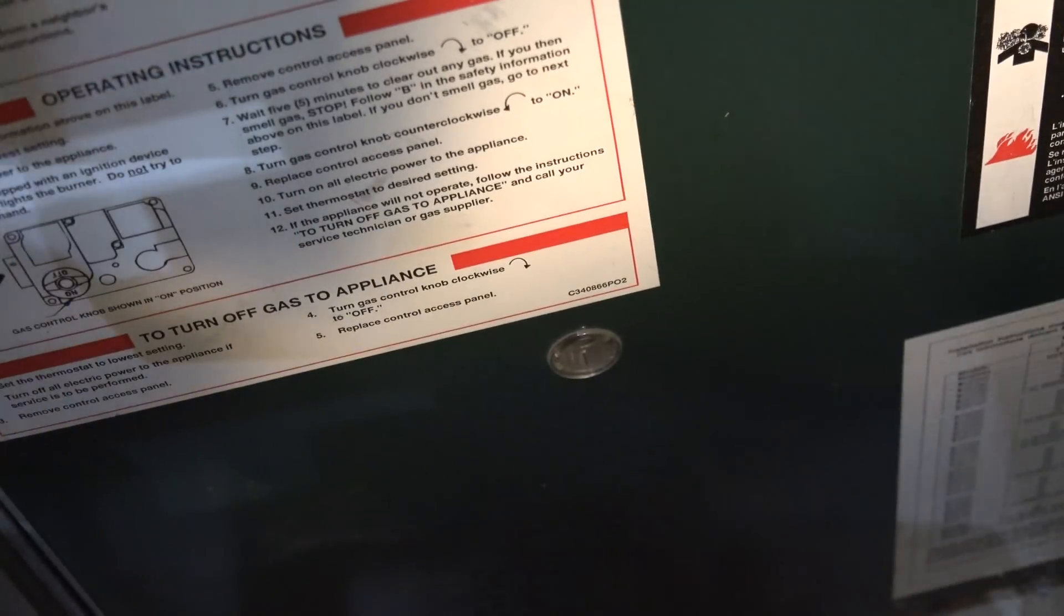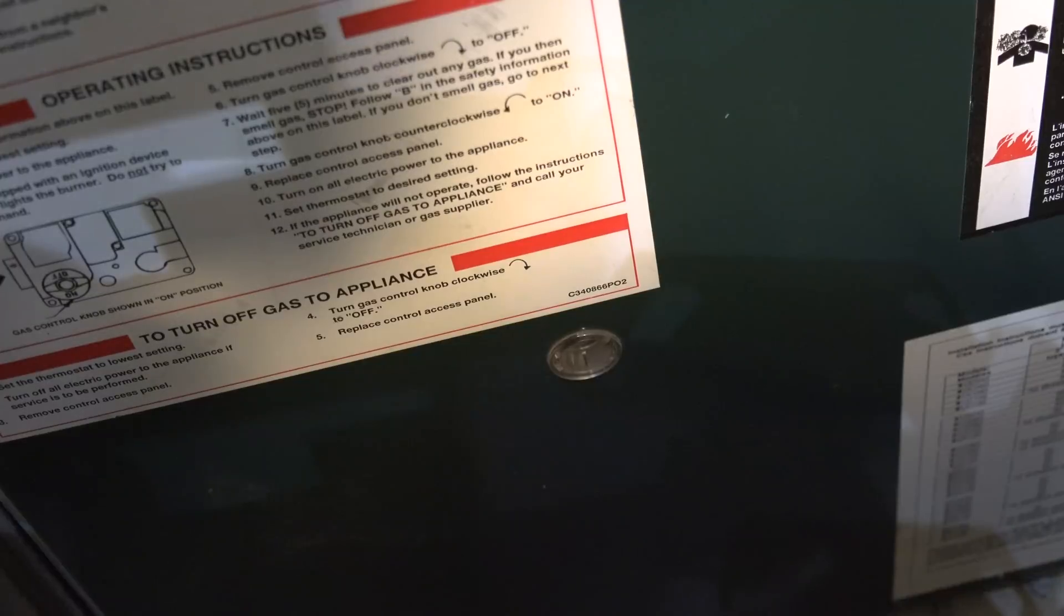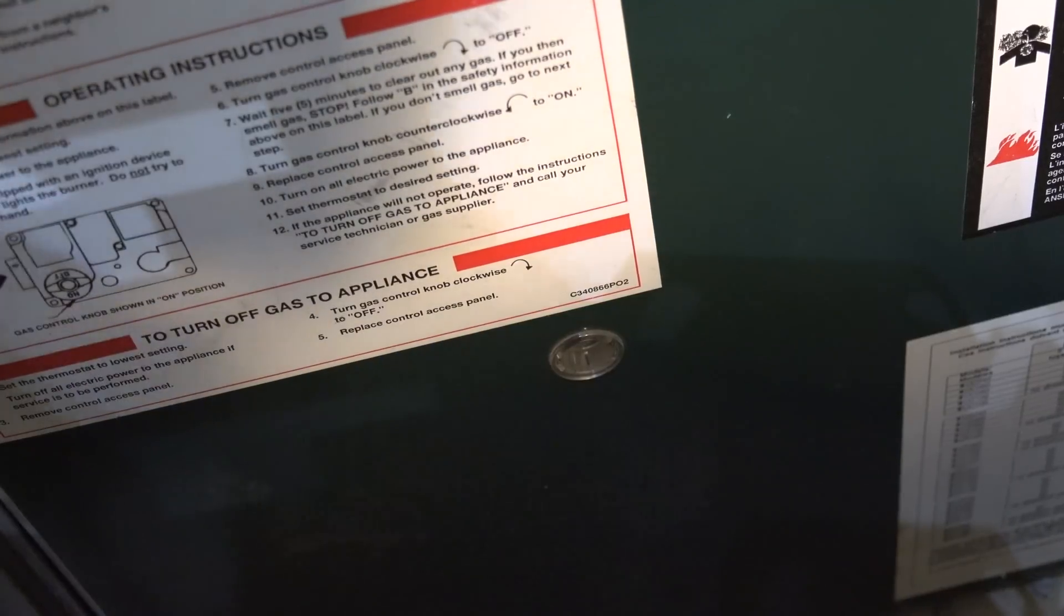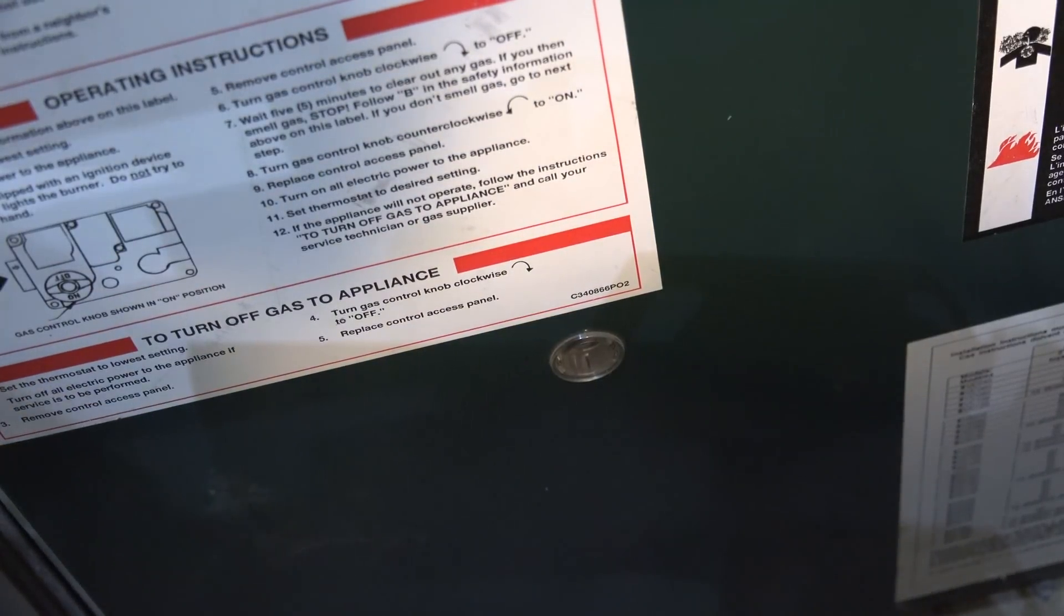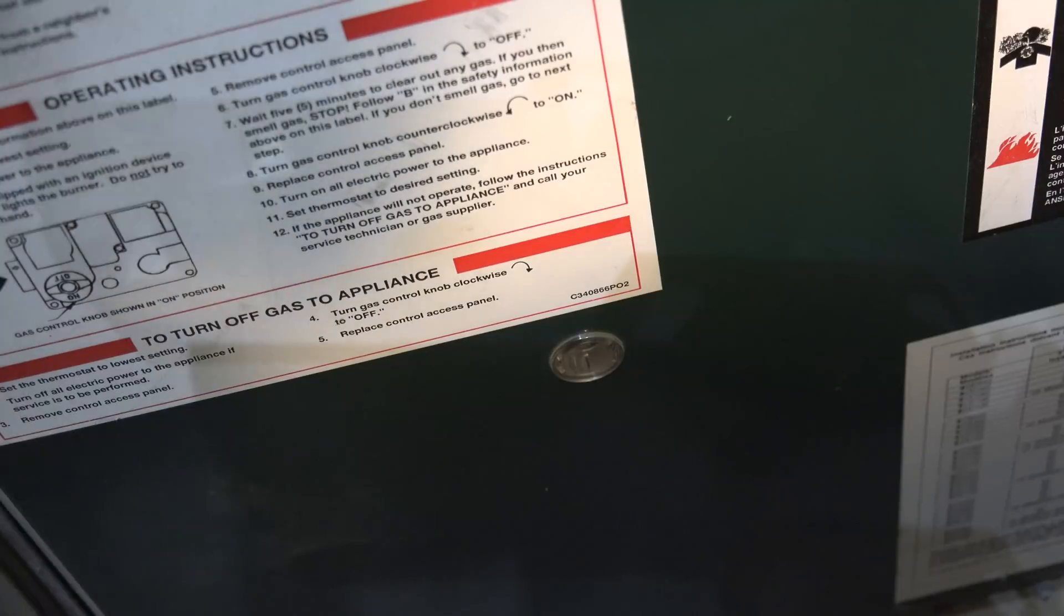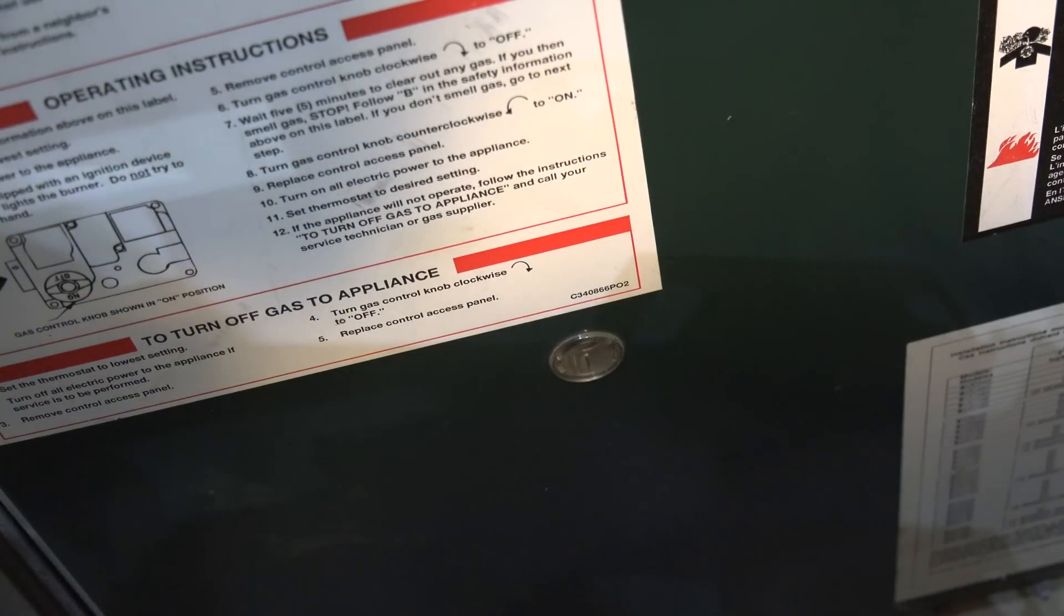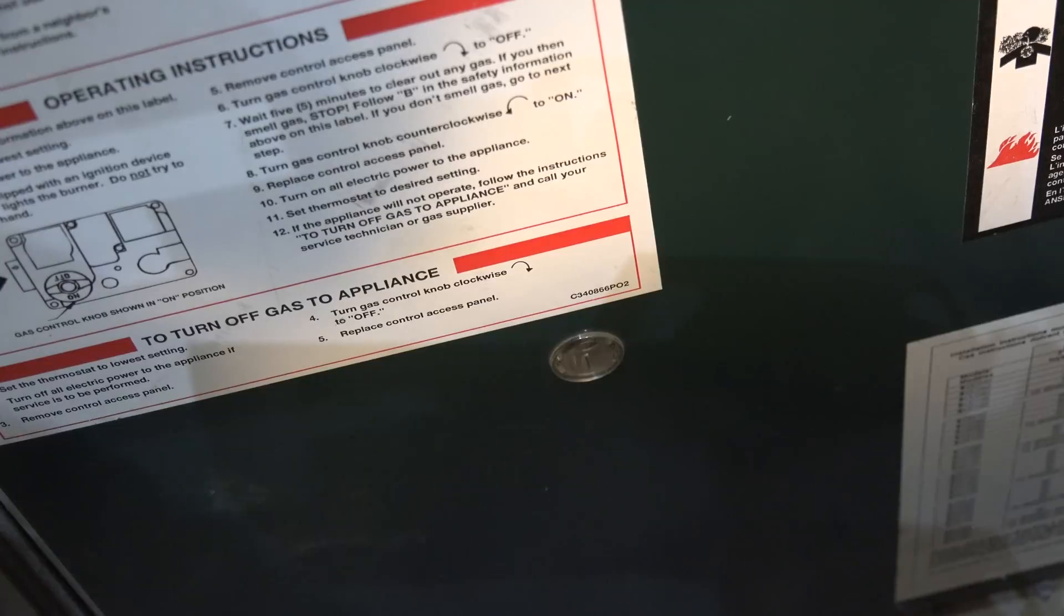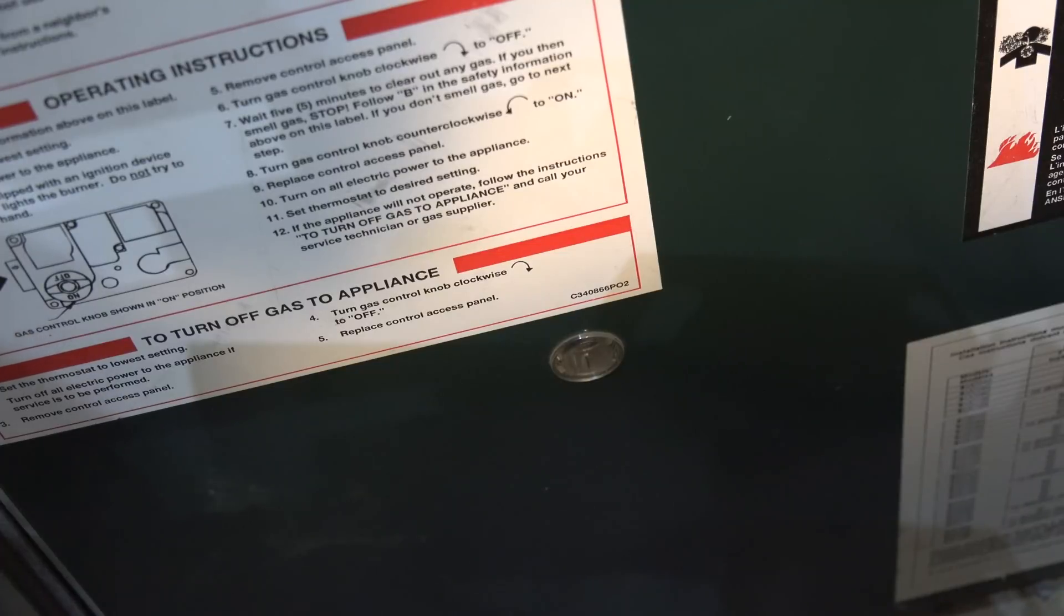Now the next thing you're going to do is look down for that little window right there. I'm not going to try to get in front of it, but as soon as this thing tries three times and shuts down, it is going to start blinking you a flame failure code. That's what you're looking for. That means it's gone into hard lockout. That means it's working normally.